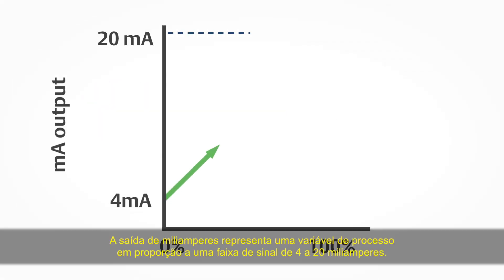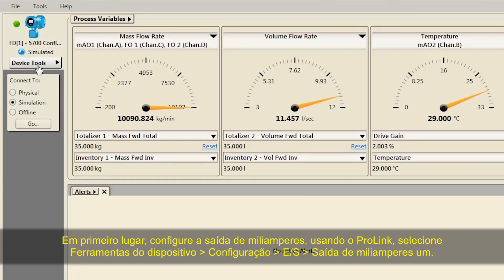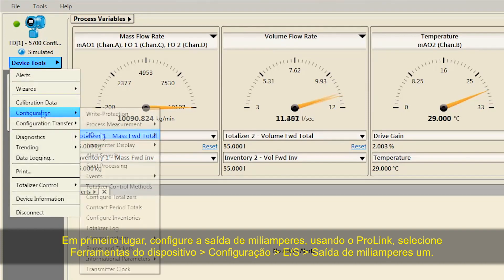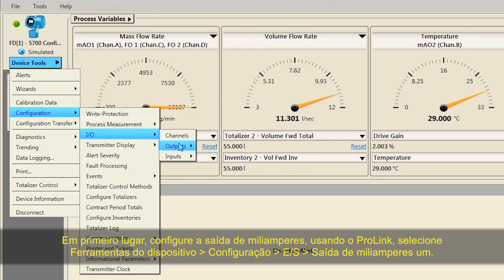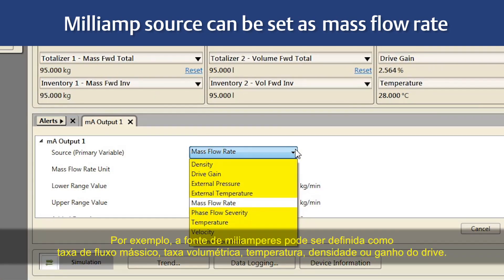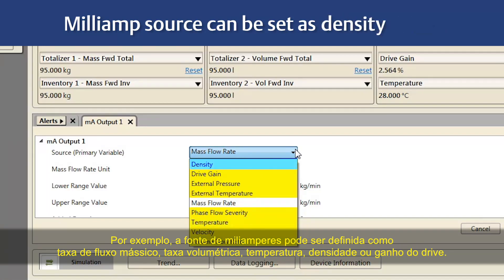The milliamp output represents a process variable in proportion to a signal range of 4 to 20 milliamps. First, configure the milliamp output: using ProLink, select Device Tools, Configuration, I-O, Outputs, Milliamp Output 1. For example, the milliamp source can be set as Mass Flow Rate, Volume Rate, Temperature, Density, or Drive Gain.